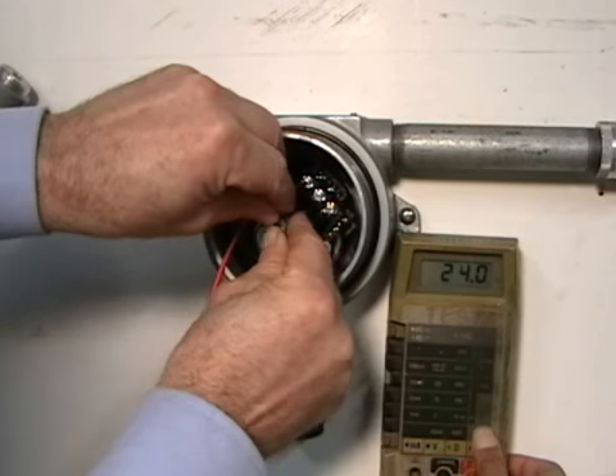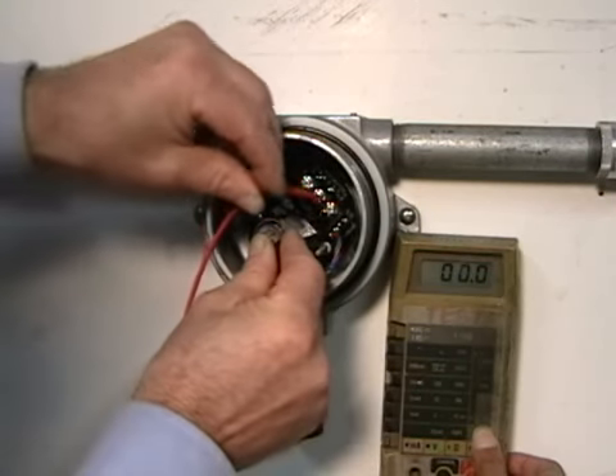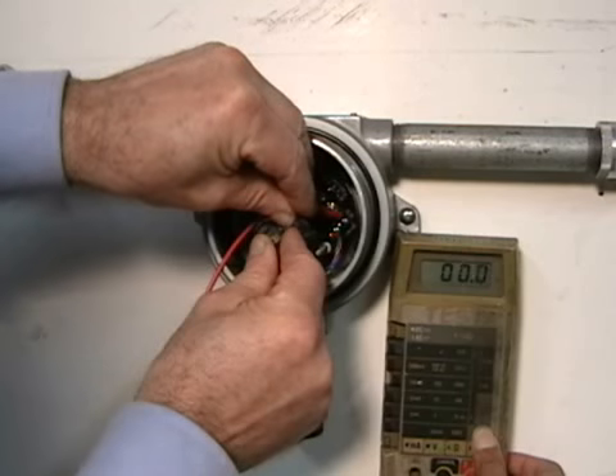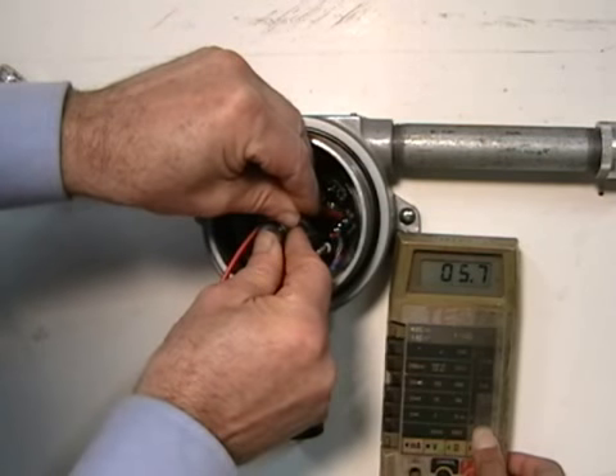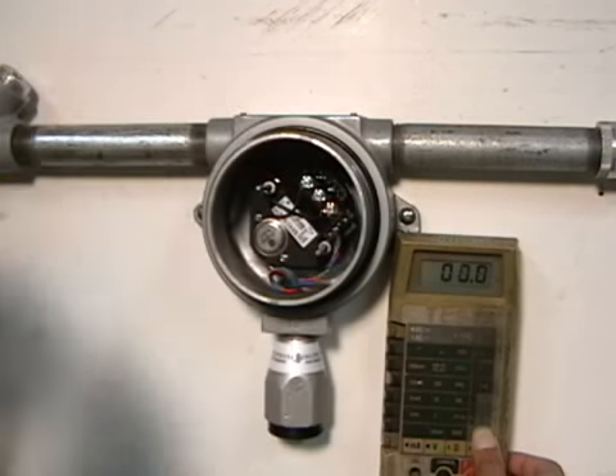At this time, you can also verify the sensor is operating at approximately the correct voltage by probing the black and red wires of the 4-pin sensor connector. Typical good values are 5.6 to 6.4 volts.